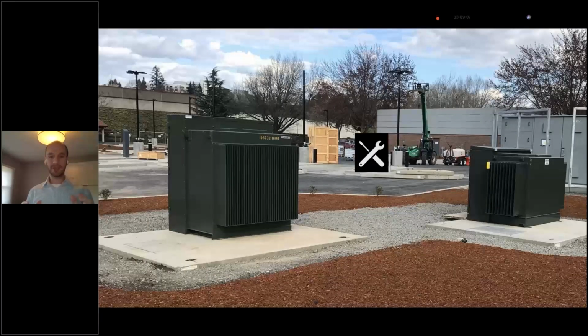Right now, the transformation installed in this location is rated for about 2 megawatts. Each transformer can handle about a megawatt of capacity, but they're sitting on vaults that enable installation of much larger transformers, 2.5 megawatts each, getting us to that 5 megawatt level. This makes it easy for utility crews to come out, pick up these smaller transformers, and drop off a larger one as the site's power output increases in the future.